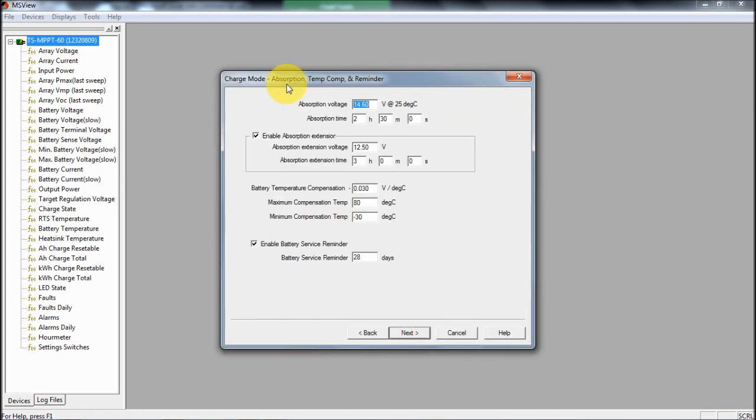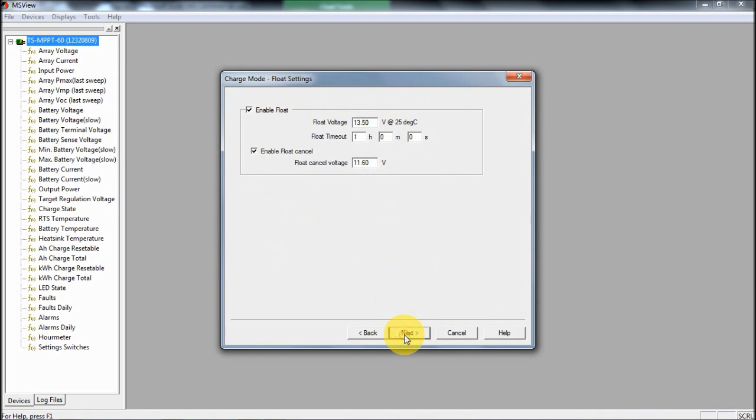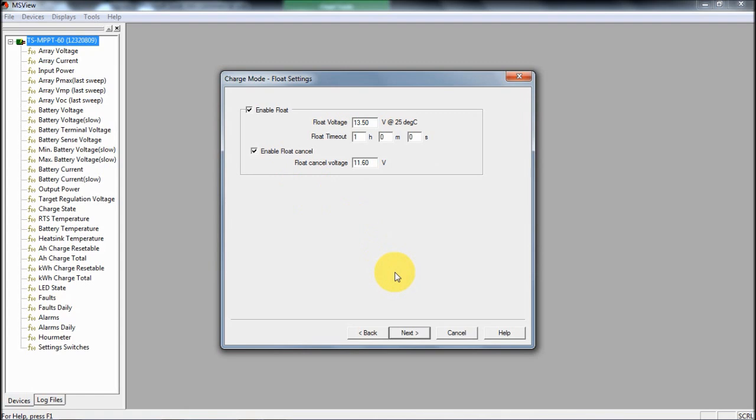You can see here you go through all kinds of variables. I'm not going to talk through these. I'm not going to give any advice on what would be the right settings for you, because this is completely custom to every system, and you really do have to be careful. If you get this wrong, you could cause some pretty serious problems. But you've got everything from setting the absorption voltages, temperature compensation, reminder for doing battery services. You can look at what level you do a float charge at. Interestingly, the float cancel is actually saying if the battery drops below this voltage, then the following day you don't do float charge at all. You just absorb all day to help the battery recover from its deep discharge.